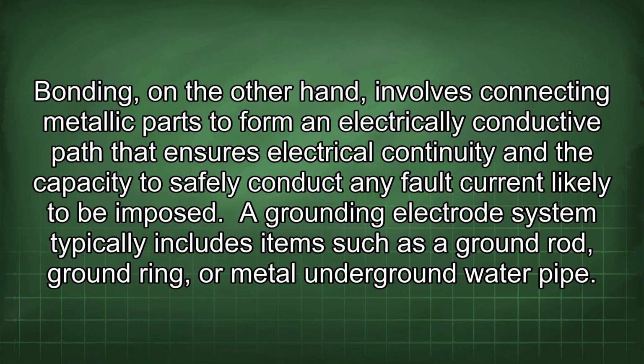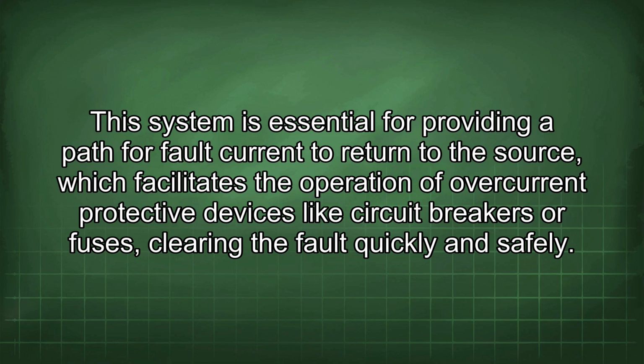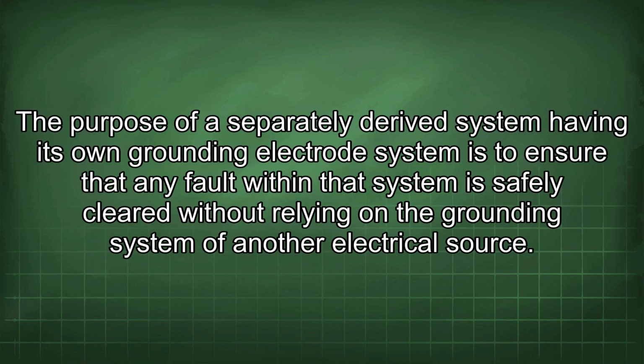A grounding electrode system typically includes items such as a ground rod, ground ring, or metal underground water pipe. This system is essential for providing a path for fault current to return to the source, which facilitates the operation of overcurrent protective devices like circuit breakers or fuses, clearing the fault quickly and safely. The purpose of a separately derived system having its own grounding electrode system is to ensure that any fault within that system is safely cleared without relying on the grounding system of another electrical source.